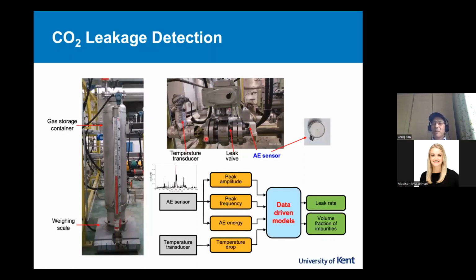We tested the methodology, again, just like flow measurement, deploying data-driven models. We extract features from the acoustic emission signals in the time domain and frequency domain, and you can see here we also incorporate the temperature output. All this information is combined and input to the data-driven models, so we can predict the leak rate and even the volume fraction of impurities, if any.